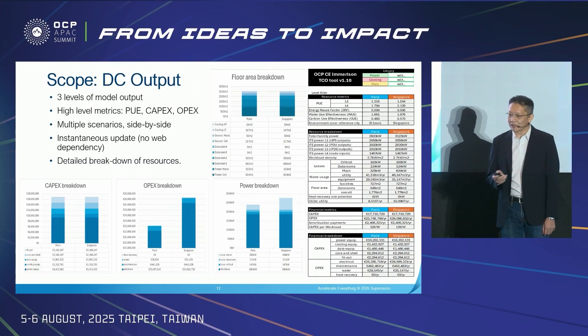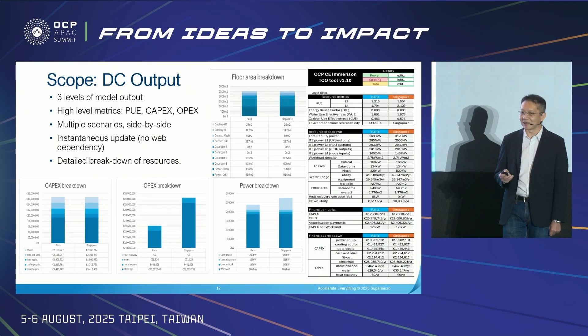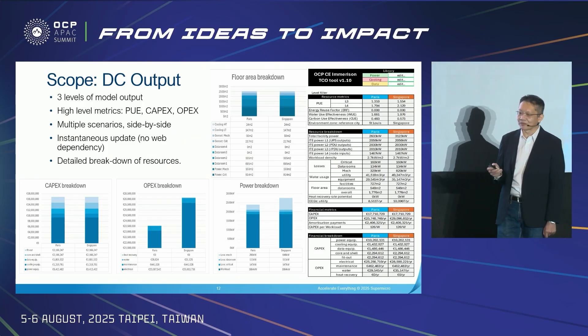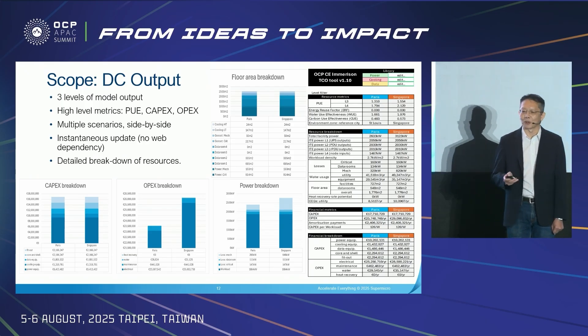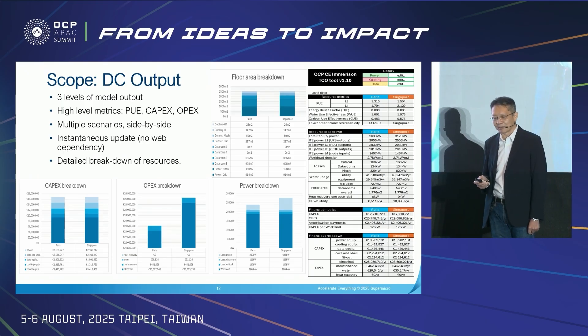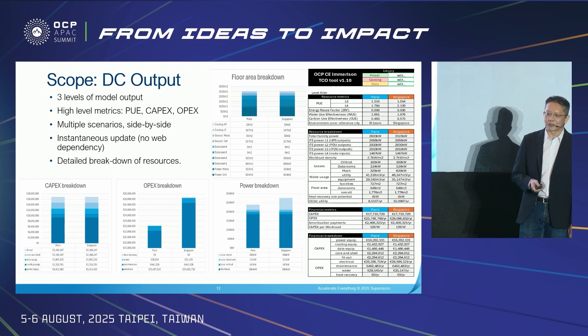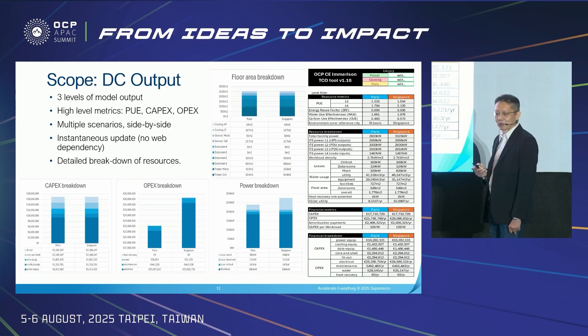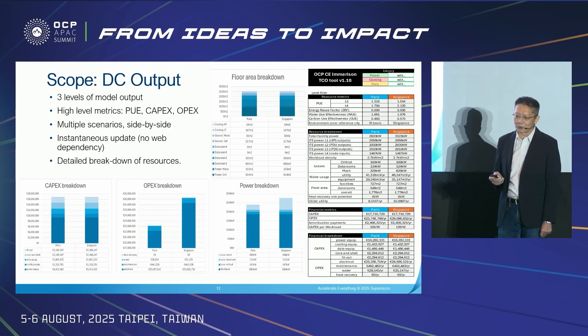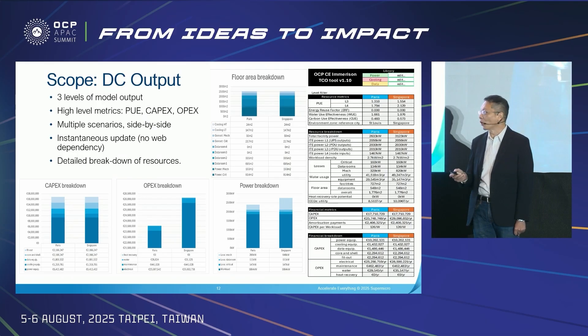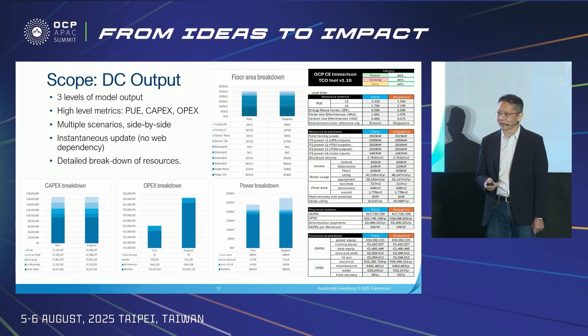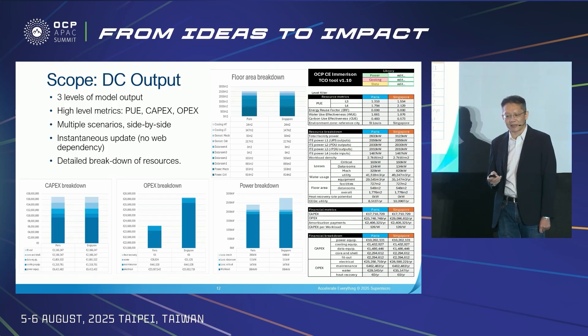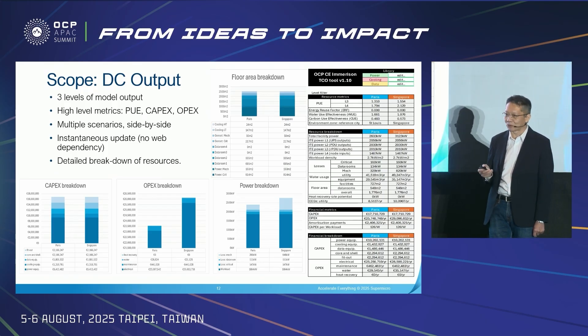The tool outputs key efficiency metrics from the scenarios modeled: peak and average PUE, energy reuse factor, water use efficiency, CUE, and workload density. It also outputs key financial metrics: CapEx, OPEX, amortization payment, and CapEx per watt of workload. In addition, it reports resource usage such as power, cooling, and floor space. Furthermore, the tool offers a detailed financial breakdown, showing how equipment and building costs contribute to CapEx and how resource overheads contribute to OPEX.